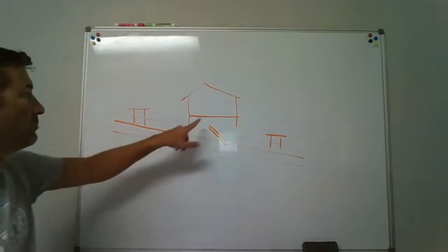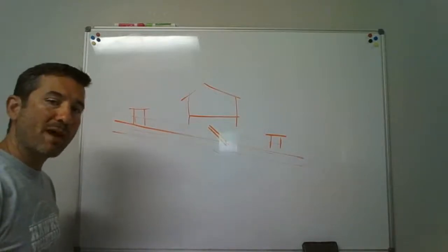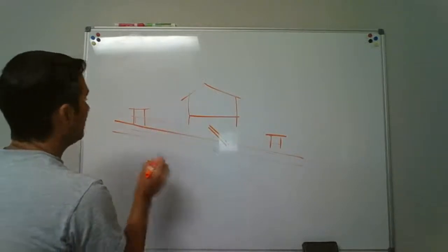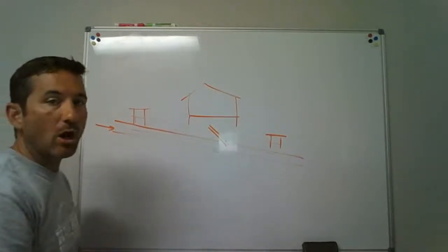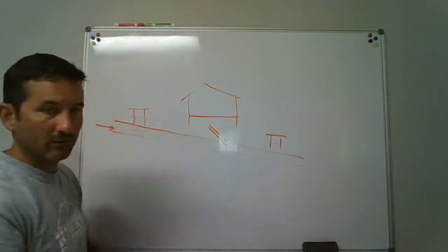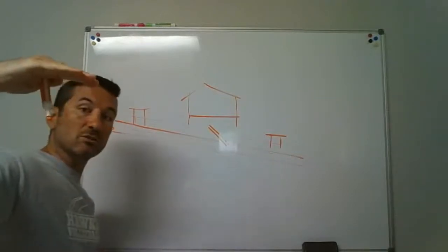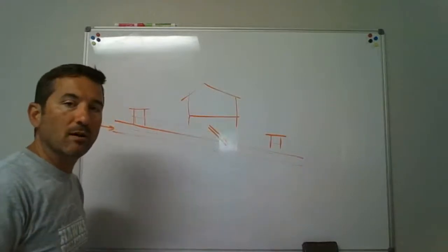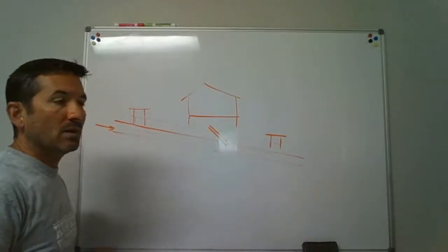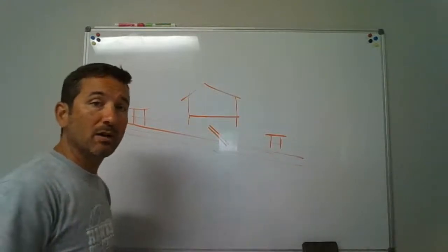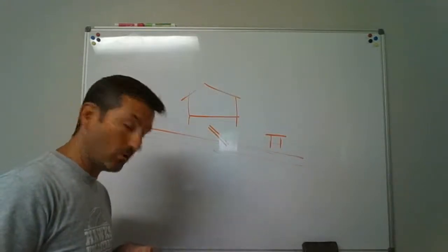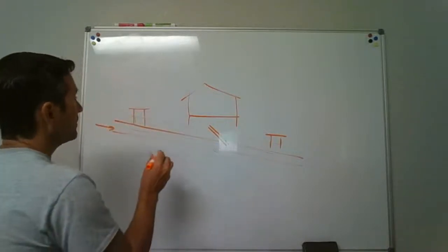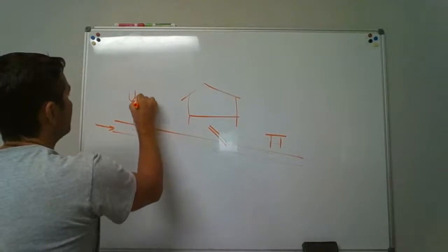Okay, so what we do is when we come out and we try to determine, does this house need a backwater valve? You come out and you look at the upstream manhole. Now, I drew this to where it's very obvious. It looks like everything's flowing this way, and you could see the street is kind of heading down, so it's typically going to follow the grade of the ground. If it's really, really level and flat out there, you might need to get them to mark it, or you can lift a manhole and look down in and just see which way things are flowing. But in this case, here's your upstream.